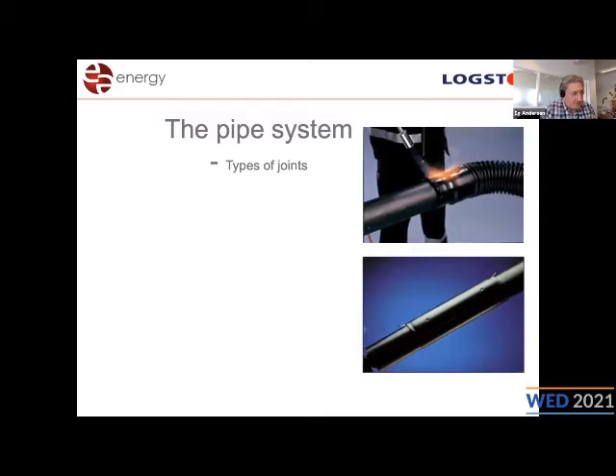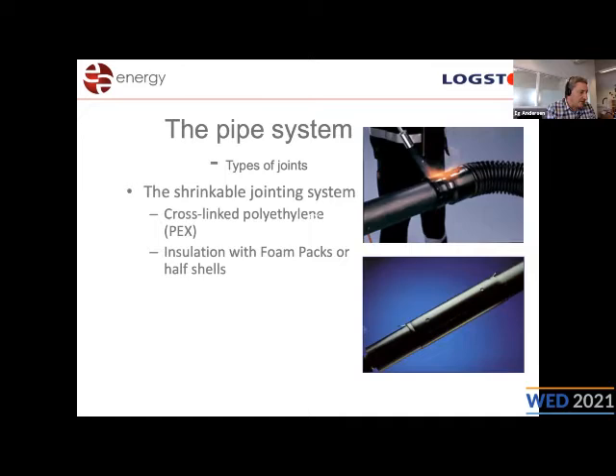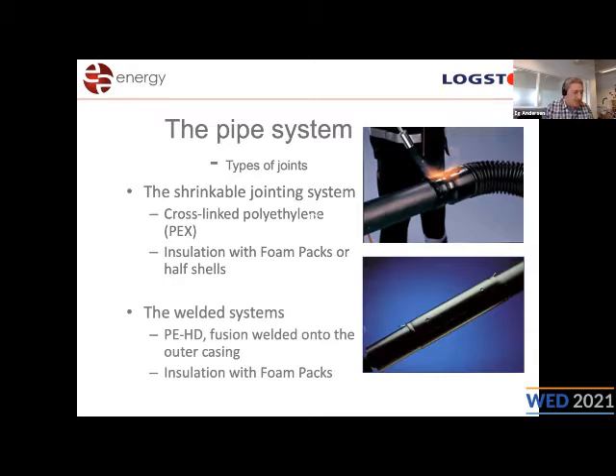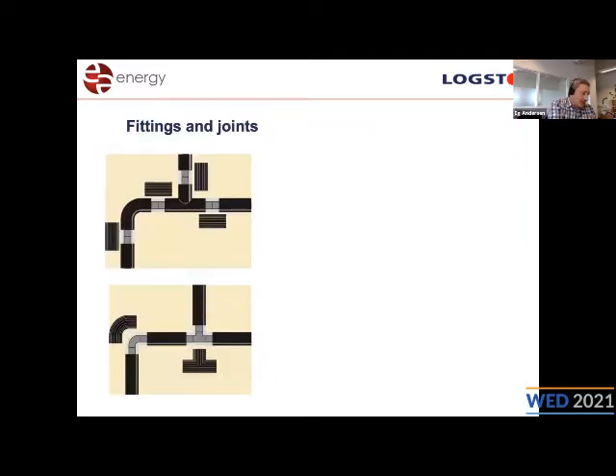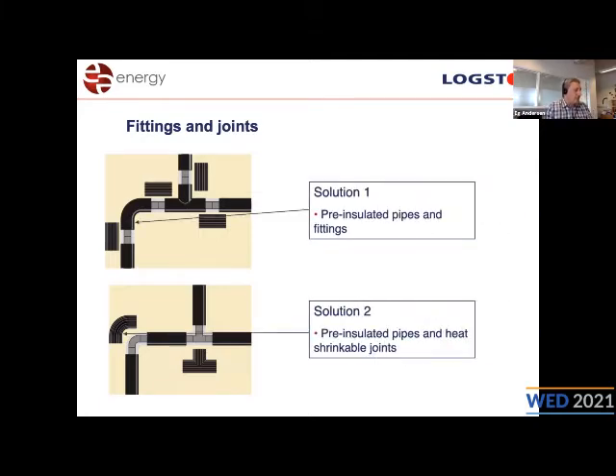How do we install them? Well, we have 2 half shells and we put them around the media pipe, and then we shrink it down either by a shrinkable joint system, or we have the welded system where we weld it with these 2 electrical wires you see here. Then it shrinks down, and then we fill out these holes with polyurethane foam. So I know it's a lot of information about joints, but it's a very important part of our pipe system. And this is basically how it's done.